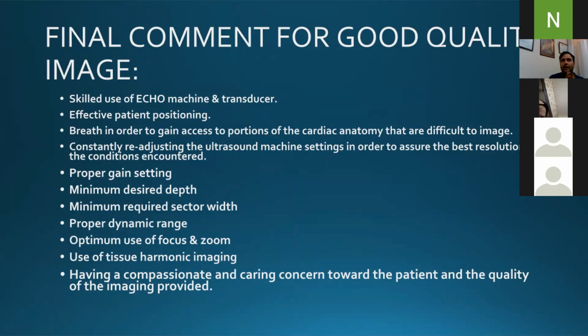Sector width should be lesser so as to accommodate only the area of interest. Frame rate should be as high as possible. See, there's not a separate button for frame rate. Frame rate increases when we decrease the sector width and when we decrease the depth. Frame rate increases, right? So at least a frame rate between 30 to 40 or more than 40. The higher the frame rate, the more acceptable it is to us, but it shouldn't be less than 30.